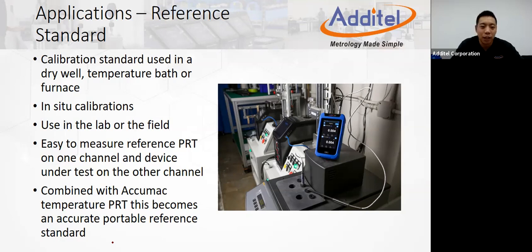The first one is what we call the in situ calibration. So in situ calibration is something like the reference is put directly in the process without removing the DUT. So we can say that the reference is usually very close to DUT, and your DUT is still on the line. For example, there's a line and your DUT is definitely on the line already. So for the in situ calibration, you don't have to remove the DUT. You just need to put your standard connect to the line directly. So this time, your DUT and standard use the same heating source, and this heating source is your line.